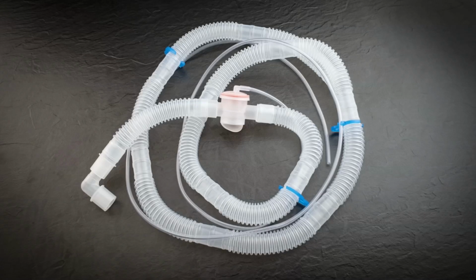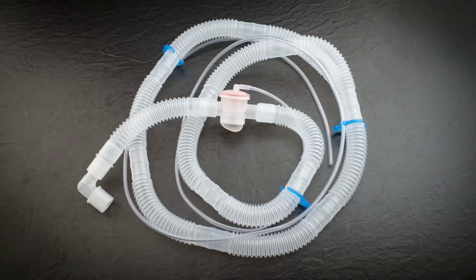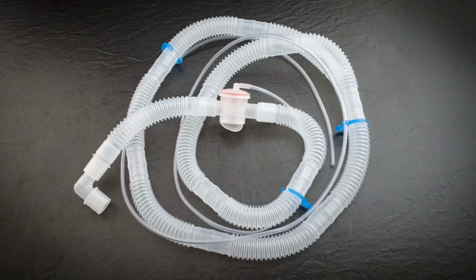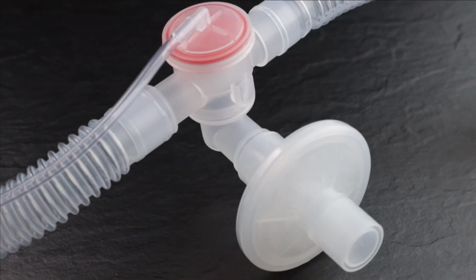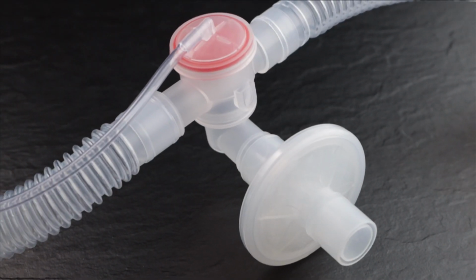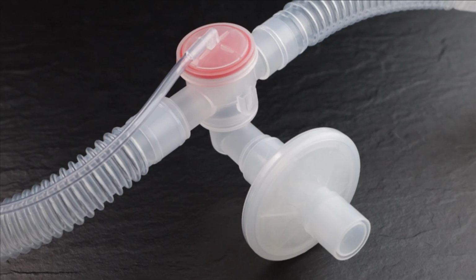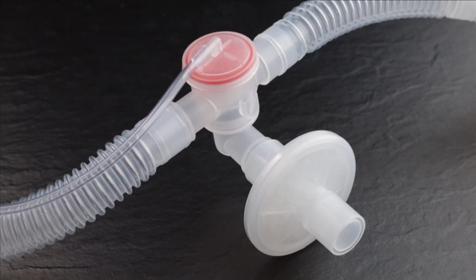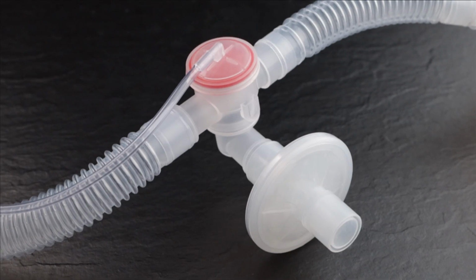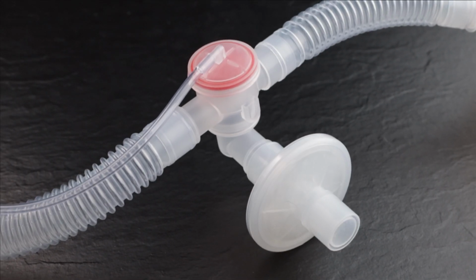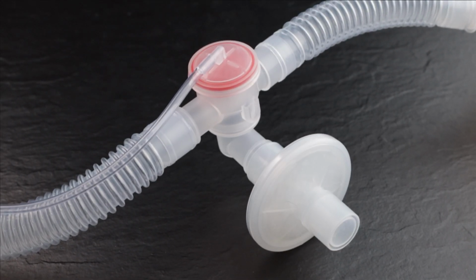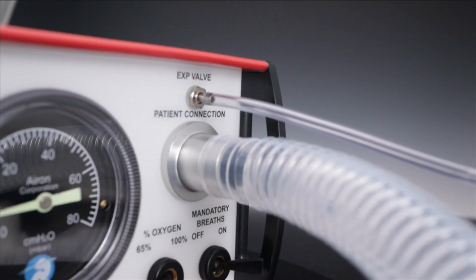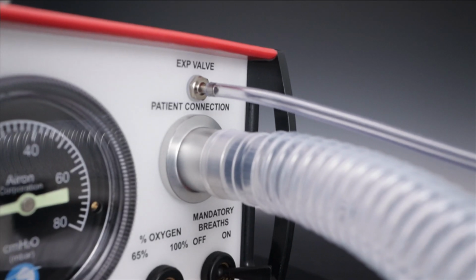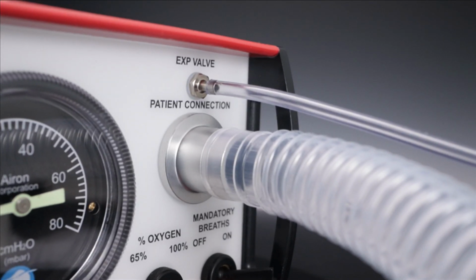Airon offers a 6-foot patient circuit as well as circuits with non-invasive mask, head strap, and expiratory filters. The patient circuit exhalation valve has been designed with an elbow to support the direct addition of the expiratory bacterial viral filter for the patient's expired gas. Simply adding this filter to the device will help you protect yourself, your team, and your patients. The patient circuit configuration is a single-limb 22mm circuit with the expiratory valve that connects to the EXP valve connection on the front of the Model S.